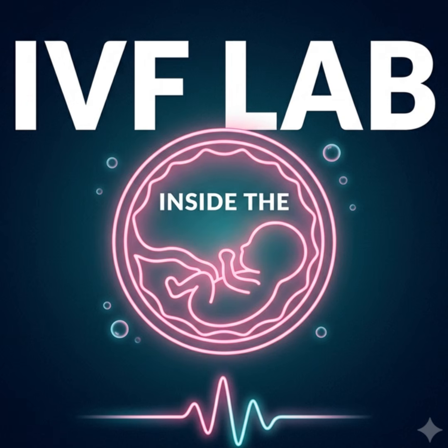Which presents a massive engineering challenge for the inverted microscope. Yeah. Because a standard microscope stage is typically just a thick slab of steel, aluminum, or standard glass. And in thermodynamics, a thick slab of ambient temperature metal is basically a giant heat sink. The moment you place a thin plastic petri dish onto that stage, the metal will aggressively conduct the heat away from the culture media, plunging the oocyte into cold shock. It sucks the heat right out. And you can't just aim a space heater at the microscope. That would create turbulent air currents and completely uneven heating. Right, you require highly localized, perfectly uniform, and entirely transparent heat.